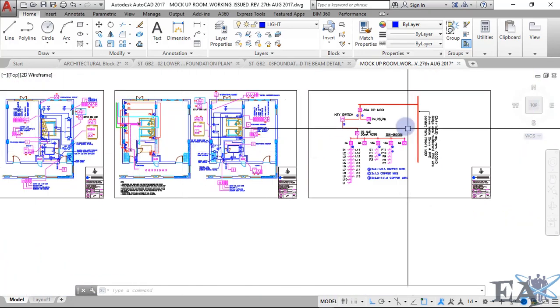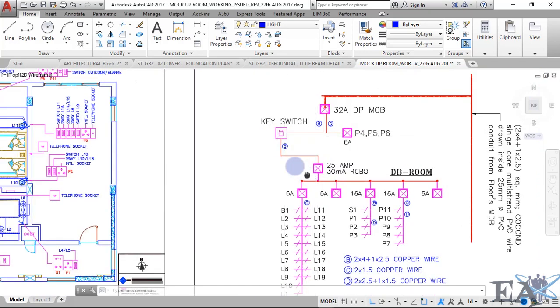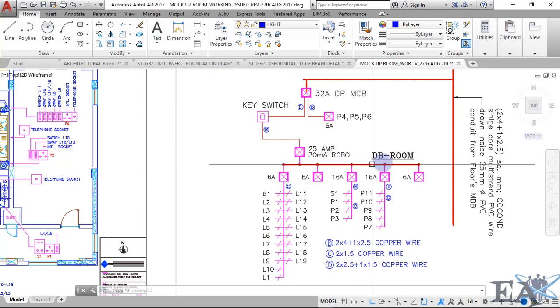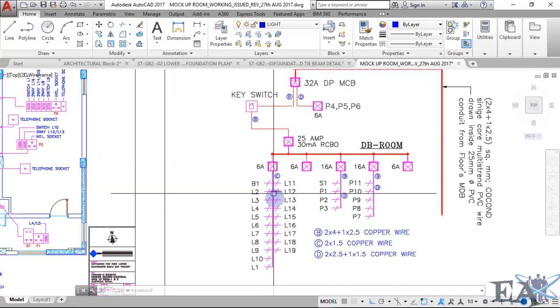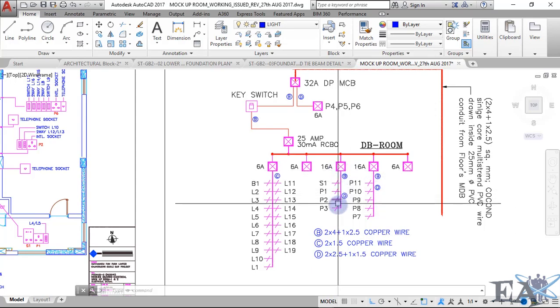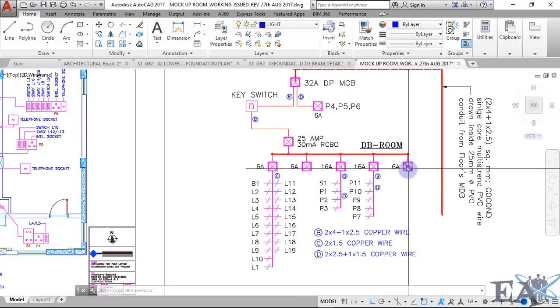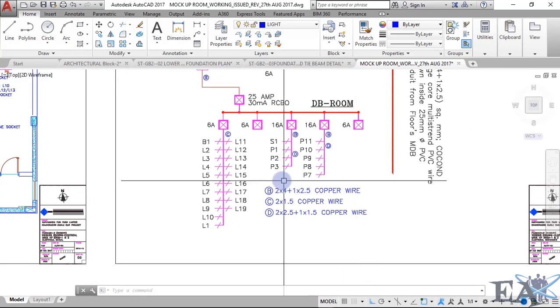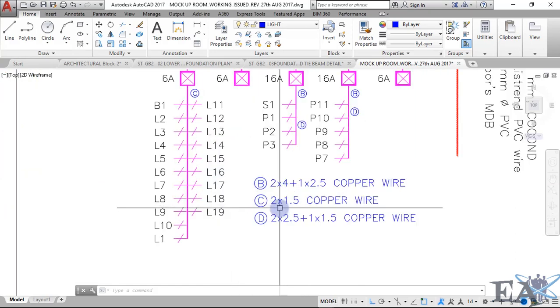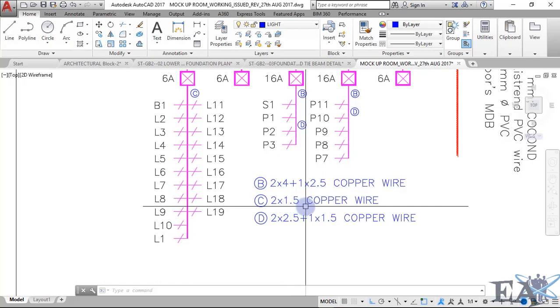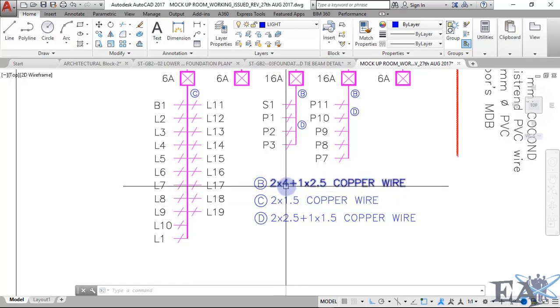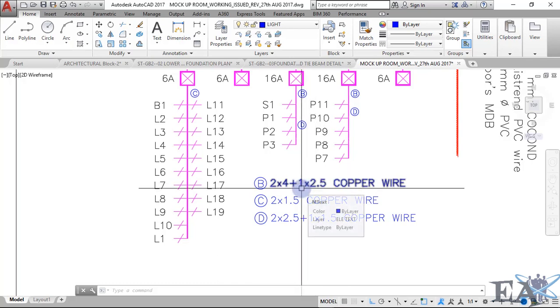From the double pole MCB, one wire goes to the key switch and another to a 6-ampere single pole MCB, from which the wire goes to power sockets 4, 5, and 6. From the key switch the wire goes to a 25-ampere RCBO. You'll have multiple MCBs — 6-ampere and 16-ampere — specifying which lights each operates, with two spare MCBs for future extensions. Wire sizing is indicated as 2×1.5mm² for two-core cables, and 2×4mm² plus 1×2.5mm² for three-core wiring.